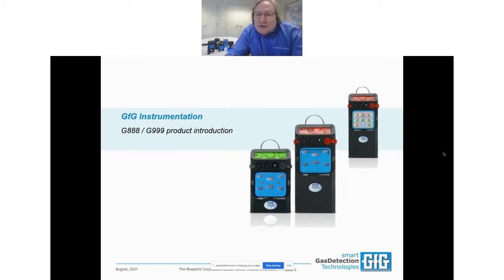The smaller of the three items on the slide is the G888. It's so small and compact, a personal portable instrument. It operates in diffusion mode only and doesn't have a pump option. Typical applications are any time you need to measure any combination of toxic, combustible, or oxygen deficiency gases, carbon dioxide—you name it, we can measure it. It is smaller than most 4-gas meters, but capable of measuring up to 7 hazards at the same time.